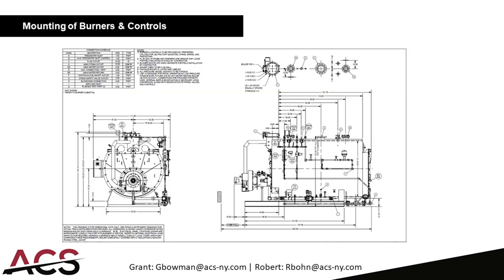Here is a typical drawing of a boiler burner package. The boiler is mounted with the burner and the gas train on the right side — though it can be right or left. The control panel is hanging off the left side as specified, but it can really be mounted anywhere. There is also a pipe coming off the exhaust of the boiler — that's the FGR (flue gas recirculation) line. FGR helps lower NOx emissions and improves efficiency by reusing some of that hot exhaust air to preheat the combustion air coming into the burner. It's a very easy thing to add and is recommended, though not required.